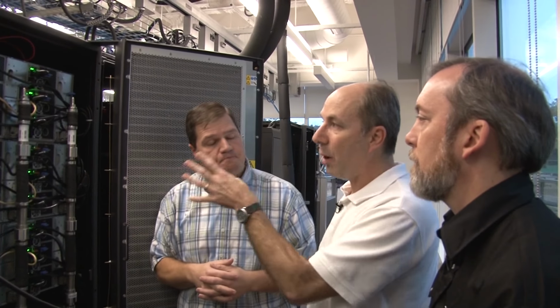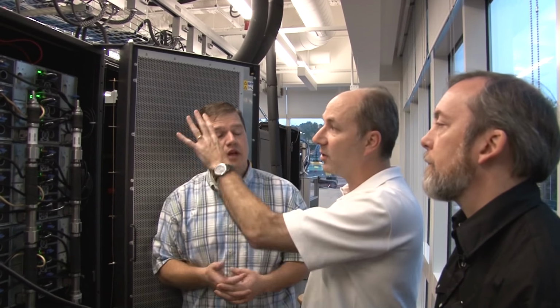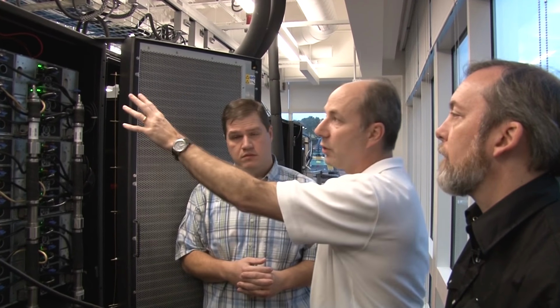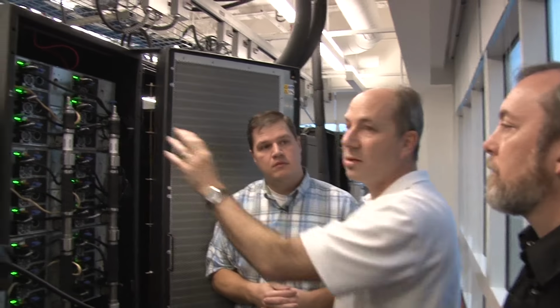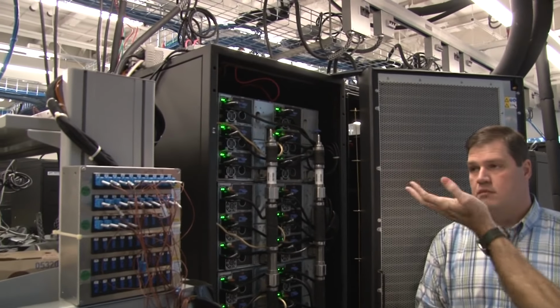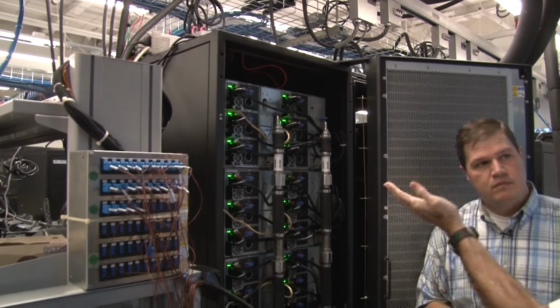So now we can remove those 10 system fans from that system and only use the air cooling from the power supply. It's actually an interesting note that a lot of the components in the water cool solution are the same ones that we use in the air cool solution. So yes, the chassis, if you look at these fan bays, those are the same fan bays that are used in the air cooled solution. We just don't need them here.